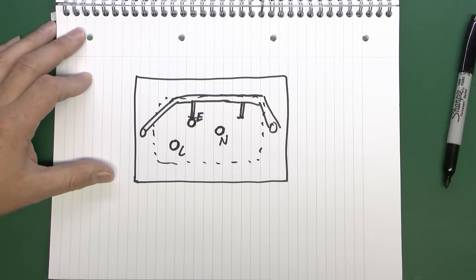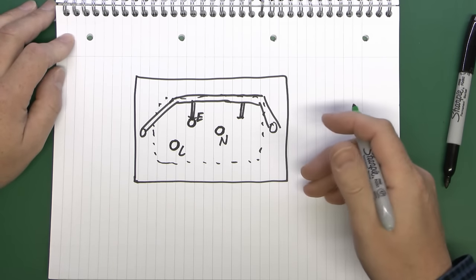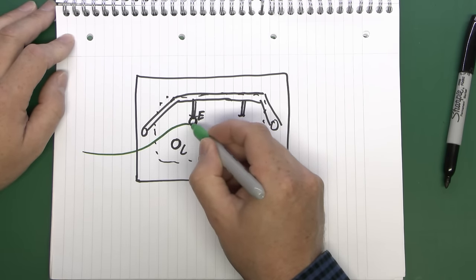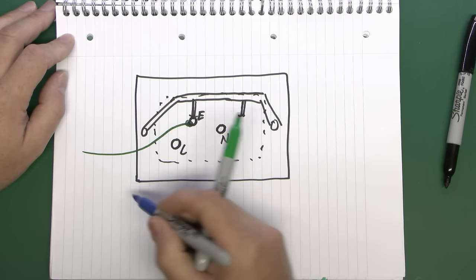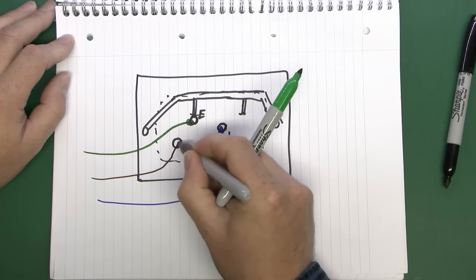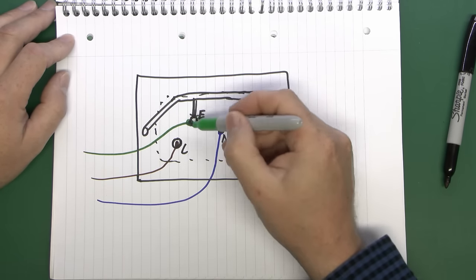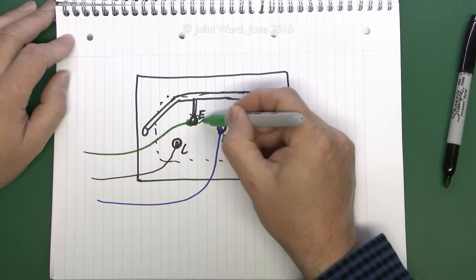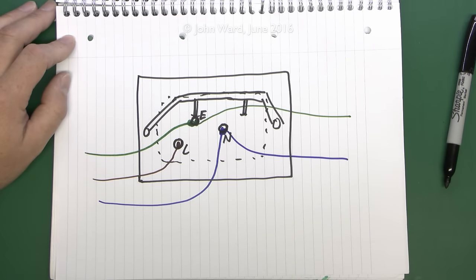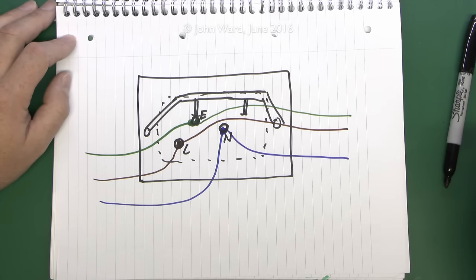In terms of the cabling attachment, it's very straightforward. If you've got two cables — one in from the consumer unit and one going out to the next socket — your earth would come in to the earth terminal, the neutral would go to the neutral point, and the line would go into the line terminal. To extend on to the next socket, you're going to have the same three conductors, so it's just a question of connecting them to the exact same terminals. The green would go on the earth, the neutral blue would go here, and the line would go to the same point, continuing on to the next socket outlet.